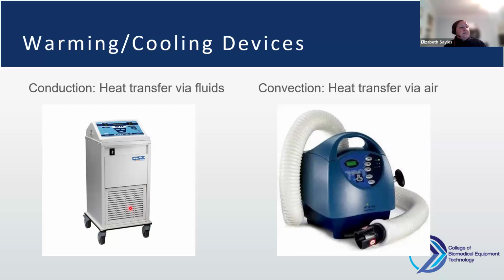Some other things you might end up doing, like cleaning the condenser. You'll do function testing of the device, so you'll have some type of temperature measuring device. A lot of the Fluke multimeters come with a thermistor probe that you can use to measure the temperature of the fluid just by wrapping it inside of the blanket, meaning the thermistor, and you can verify the temperature that way. You'll be measuring under and over temp alarms on these devices. So with these conduction units, there's a lot of maintenance involved.